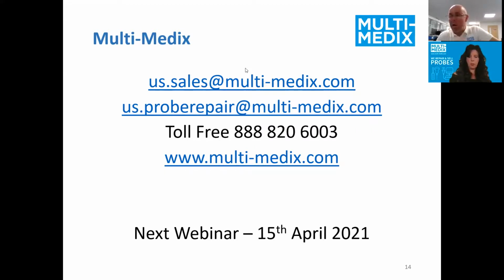One question was, what about testing matrix probes that the FirstCall doesn't support? That's a good question, Jen, because the FirstCall is a fabulous system. It does test a few of the matrix probes, especially the GE ones like the M5 SCD, which I would call a 1.5D probe due to its configuration of elements with 3 rows. However, when we get into the high density matrix probes that they now make, such as the Philips X51, there isn't a commercially available solution for that.